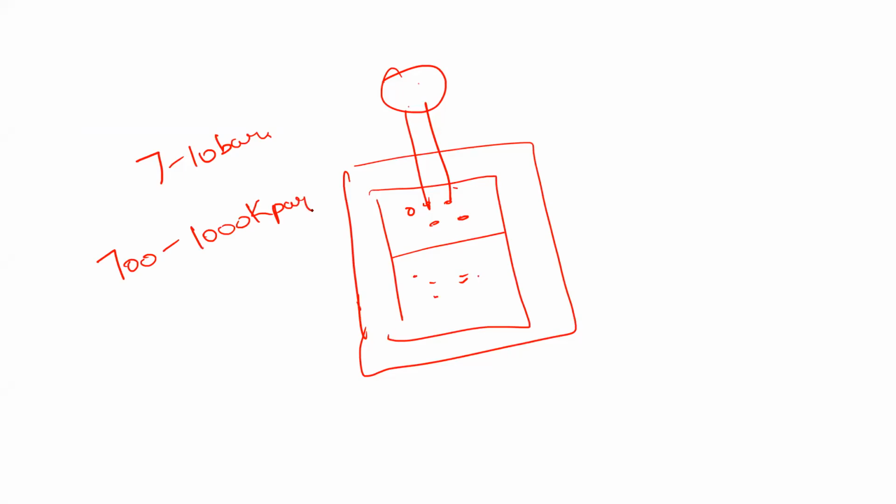Right? So normally the oxygen vaporizing chamber is kept at this pressure. Then there is a safety relief valve present here. This will open when the pressure extends beyond 17 bars or 1700 kilopascal.